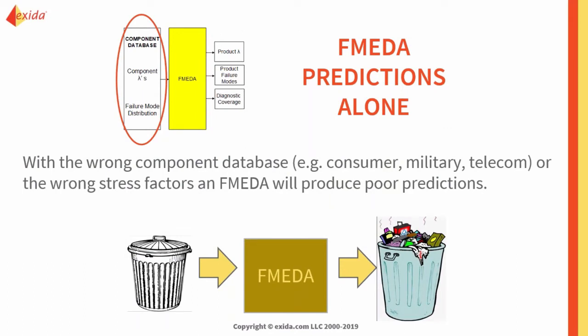As I said earlier, there are pros and cons with everything in life, and FMEDAs are the same way. The FMEDA's strength is not only how the analysis is done, but also the component database behind the FMEDA. So when you are looking at a FMEDA or having a FMEDA done, make sure and ask questions about their component database. Make sure it's going to be an apples to apples comparison with the environment, with the application, with the stress factors. If you are a subsea valve, having a telecom field study comparison for a database is not going to lend you the most appropriate results.